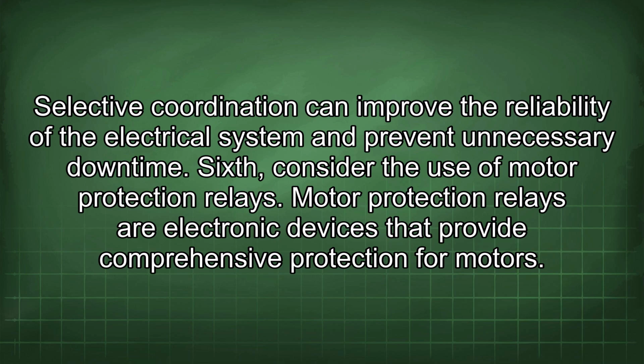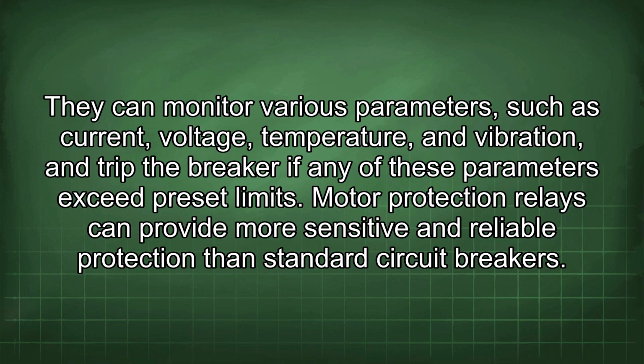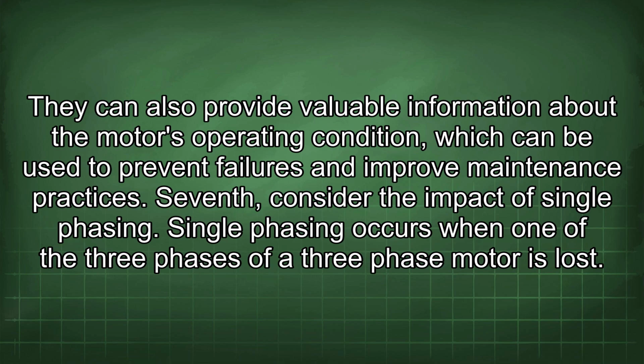Sixth, consider the use of motor protection relays. Motor protection relays are electronic devices that provide comprehensive protection for motors. They can monitor various parameters, such as current, voltage, temperature, and vibration, and trip the breaker if any of these parameters exceed preset limits. Motor protection relays can provide more sensitive and reliable protection than standard circuit breakers. They can also provide valuable information about the motor's operating condition, which can be used to prevent failures and improve maintenance practices. Seventh, consider the impact of single phasing.